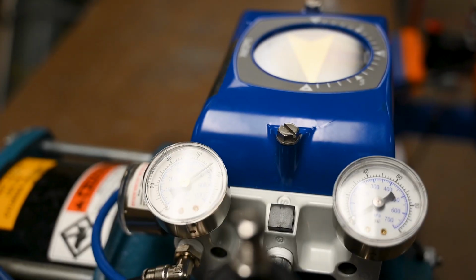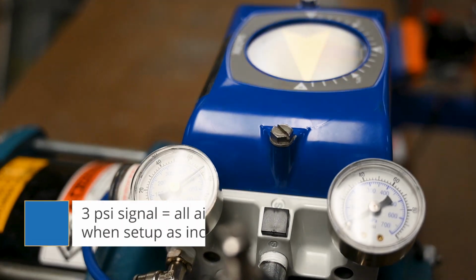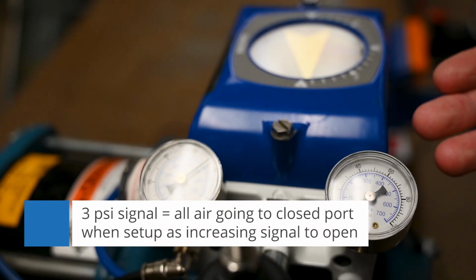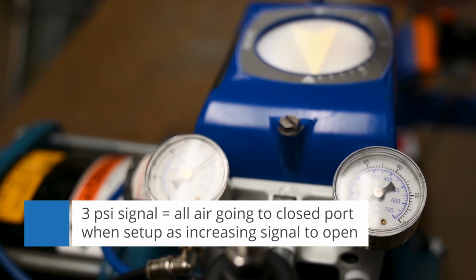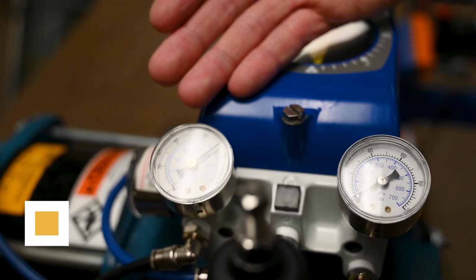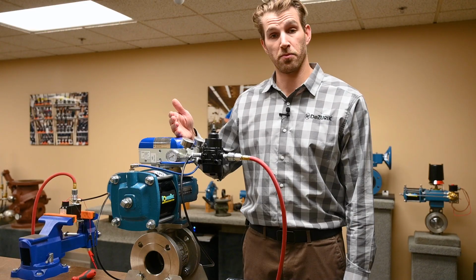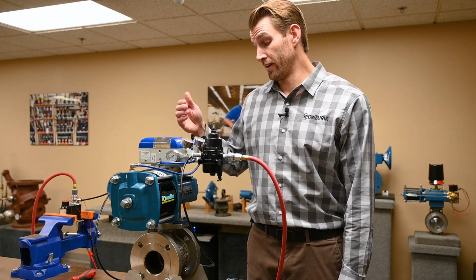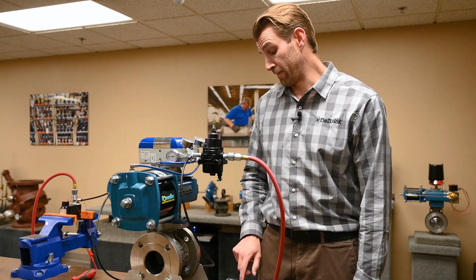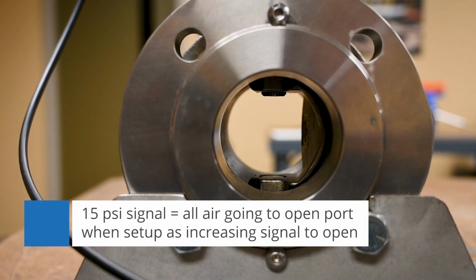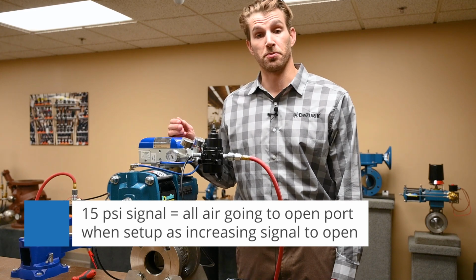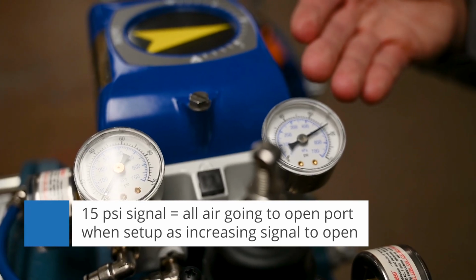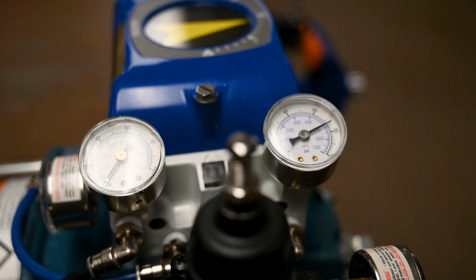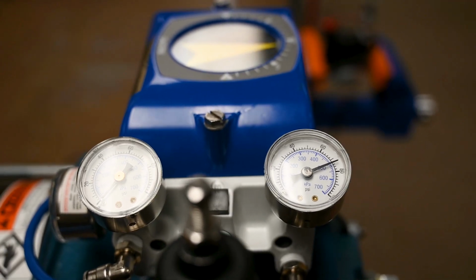When a 3 psi control signal is being sent to the positioner, all the air should be sent to the closed port of the actuator, which can be confirmed by this gauge. When a 15 psi signal is being sent, all the pressure should be sent to the open port because the valve is 100% open and there should be no pressure on the closed side, as can be indicated by this gauge.